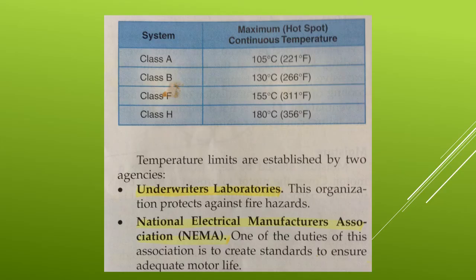Insulation systems for small motors. Four insulation systems are available for small induction motors. They are as follows. System A, or system class A, the maximum hot spot or continuous temperature is 105 degrees centigrade. Class B, maximum continuous temperature is 130 degrees centigrade. Class F, 155 degrees centigrade. Class H, 180 degrees centigrade.